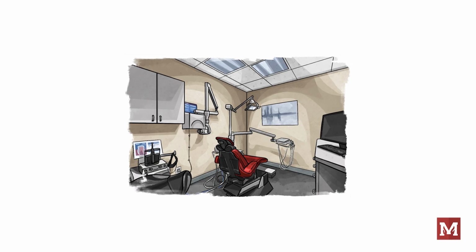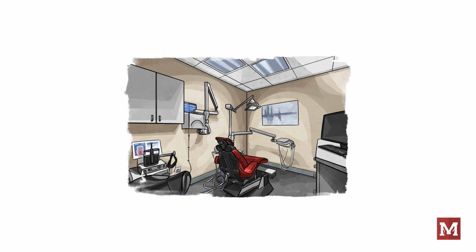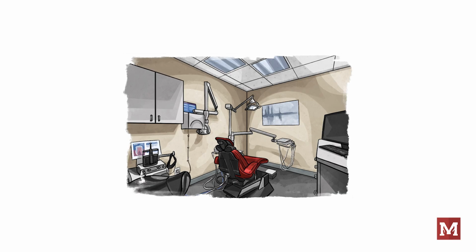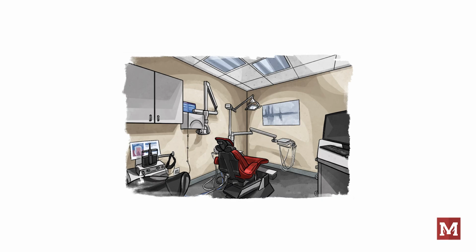So from a practical perspective, in design and review, we need to do our part to make sure we have visual coverage in the areas that it's required, and we need to account for the decorations, the furniture, and other obstructions that will likely be in that space. Does a small dental exam room need 2 strobes because there's a swinging overhead light that's mounted to the ceiling, or maybe an X-ray machine mounted to the wall that could block part of the strobe? No, that would be overkill.